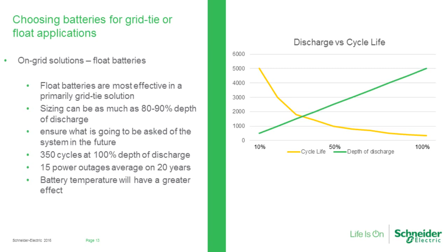We spoke in the beginning of the webinar about choosing the batteries and how using a cycling battery could suddenly make sense, especially even with AC coupling, where prices don't really diminish until past when the sun is shining. So we're actually going to leverage the system. And that's where AC coupling maybe isn't the best solution, but rather changing out that PV inverter to a DC charge controller like the MPPT 80, which is already a high voltage input, can allow you to leverage the system one step further than just backup. If the customer or the solution is expecting just straight storage, great, that's fine. But if we can use self-consumption, not today but maybe a year from now, it may be worth sizing in and using a battery-based solution that is DC coupled instead of AC coupled, so that we can take advantage of a system that's going to charge power and regulate that system completely and in a very smart way.